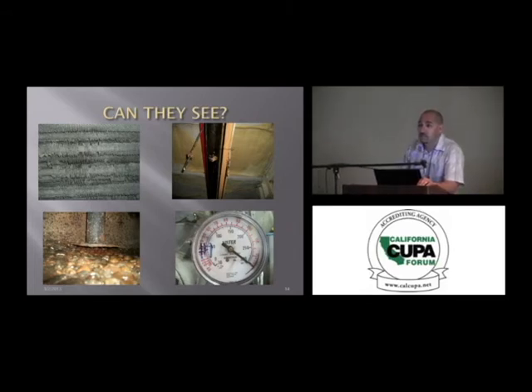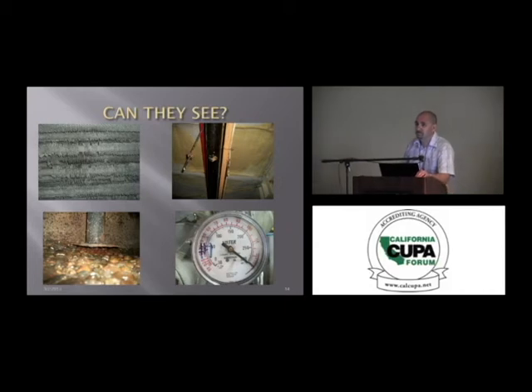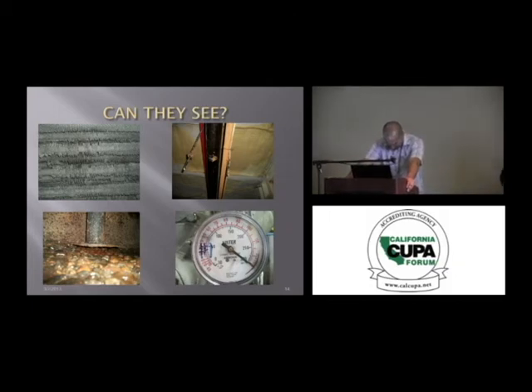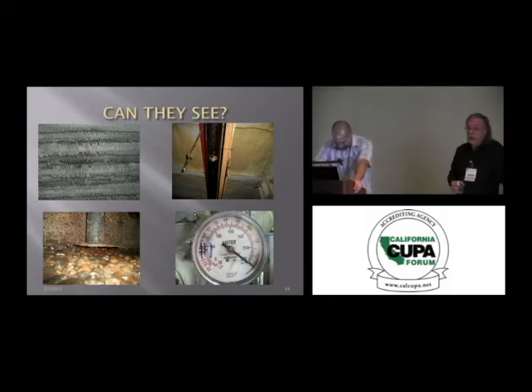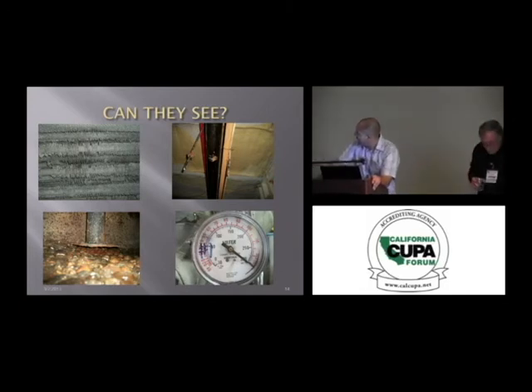A lot of it depends on where their injection points are. SO2, that's correct. Everyone I've seen where they have the injections below the coils is worse. Put it above, maybe 3 or 4 feet above it. The other thing is we recommend that plants that are using chlorine or bleach or whatever it is to clean their plants turn their air units off while they're doing the cleaning, until they do their wash down to get rid of most of the airborne material. And you can see more corrosion on the right-hand side.